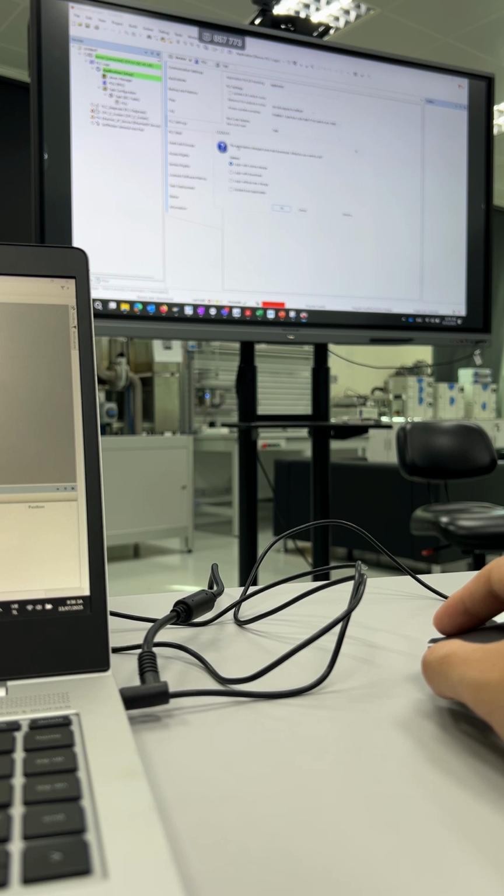But when you download with online changes, your PLC will still be in the running state. You can only log in with online changes for small changes, like just some changes in the program. If you have hardware changes, it won't allow you to download with online changes. You need to log in with download. But you need to be careful, especially if you are supporting customers: when you log in with download, it will change your PLC mode from run to stop.